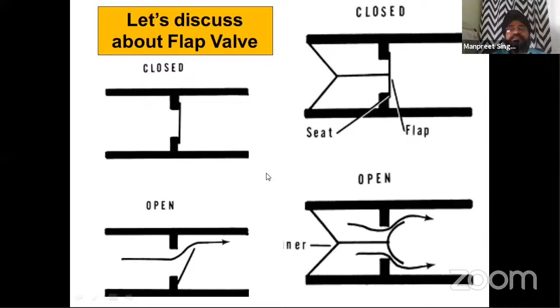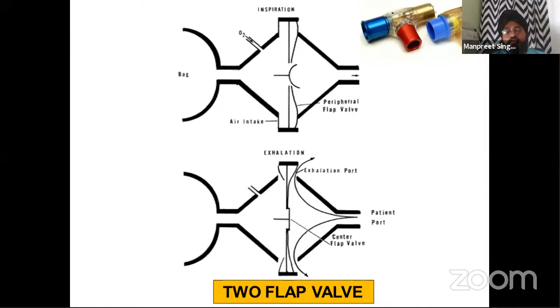And similarly, there can be two-sided flaps, there can be two flap valves, in which there is a peripheral flap valve and there can be a central flap valve. So during inhalation, the central one opens and the air goes inside. And during the expiration, what happens is the central flap goes back on the center seat, and then the peripheral ones are opened, and that's why they cause the exhalation.